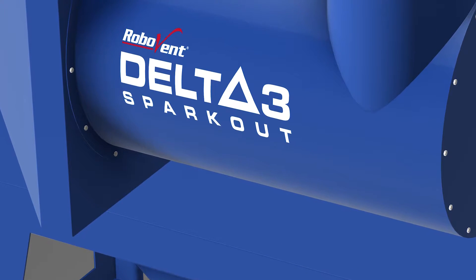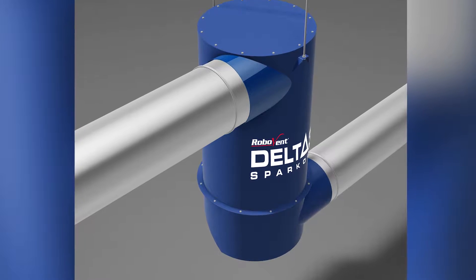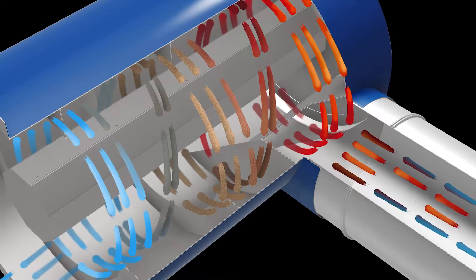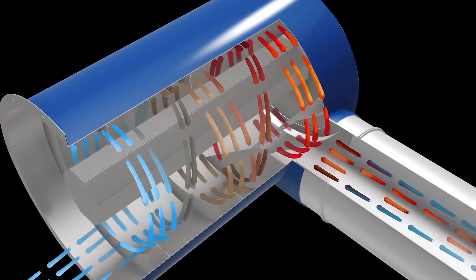The result was Delta III, an innovative design that uses centrifugal force to kill the sparks. By maintaining high velocity along all surfaces, the device is self-cleaning, and the simulations proved it would do all this with very low resistance to air flow.